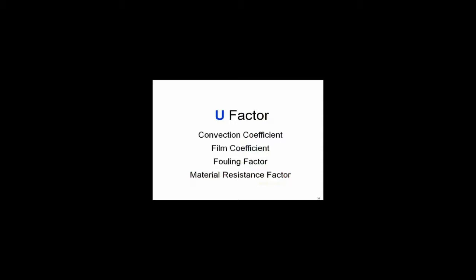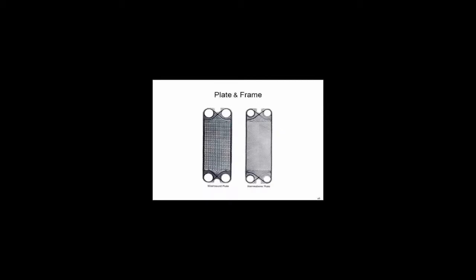So what is this U factor all about? This is the U factor that we want to look at real quick. We want the most efficient heat exchanger you can get, the highest U factor you can get. The higher the U factor, the smaller the heat exchanger, the lower the first cost, the more efficient it is. What impacts our U factor? We've got the film coefficients, which is what is on the film of the surface. Do you have turbulence or laminar flow? You've got the material resistance, you've got coefficients, and you've got fouling. You put all this together, you've got some kind of a heat exchanger pattern you're going to come up with.